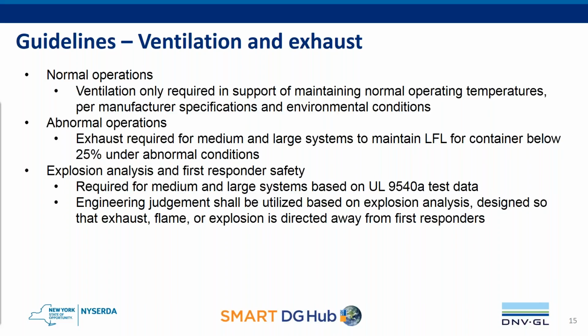Under abnormal conditions, and depending on the outcome of the UL 9540A test data, an explosion analysis would have to be conducted, and this could include exhaust to maintain the LFL in the container below 25%. And then utilizing an engineering judgment, you can conduct the explosion analysis to ensure that if there were to be an explosion, that the explosion would occur upwards rather than outwards towards first responders.